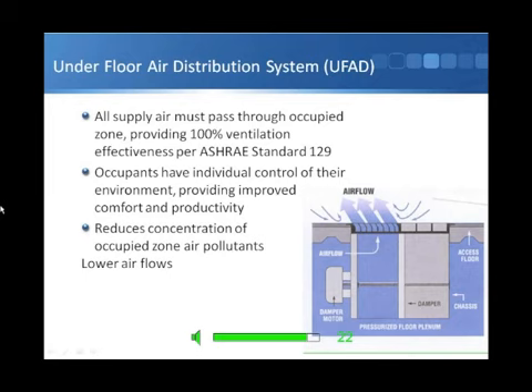I suppose just as a final point on that, I was quite interested in the presentation I did at ASHRAE on underfloor air distribution to speak to one of the other speakers from Dallas who completed a scheme, and he told me that his air volumes used in underfloor air distribution in Dallas, which is a pretty hot city, were in fact only 6 air changes an hour, as opposed to on a normal VAV or constant volume system or fan coil system, probably around 12 air changes an hour.